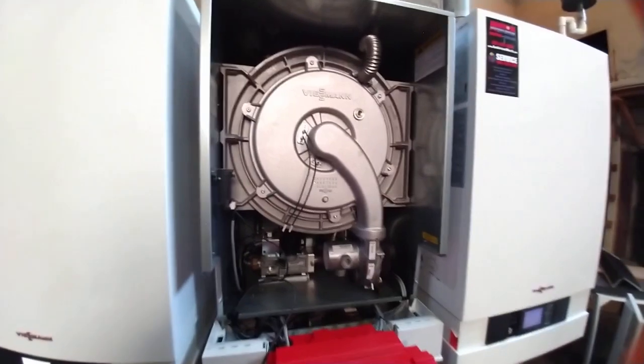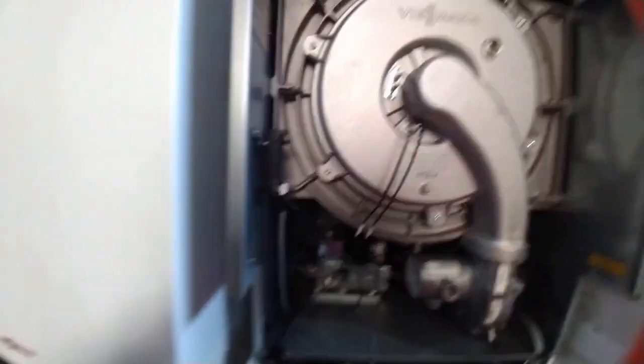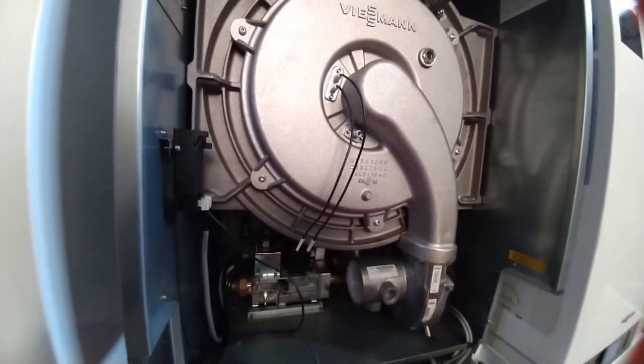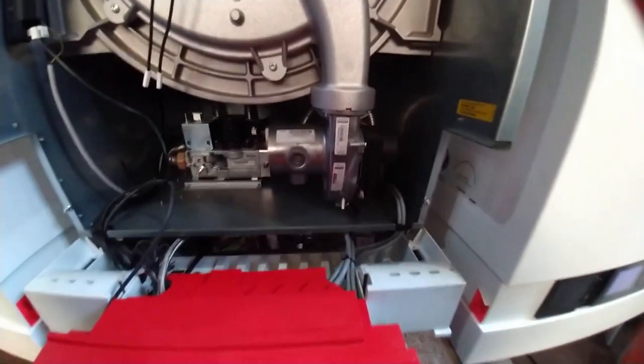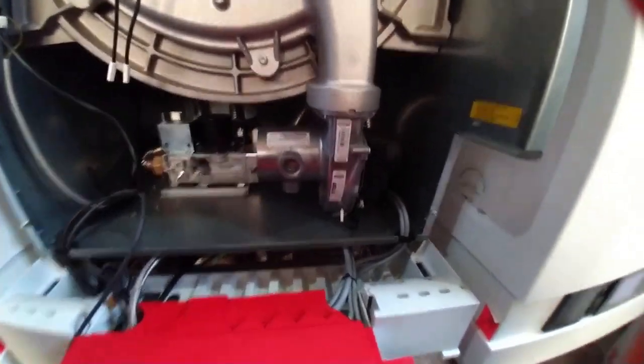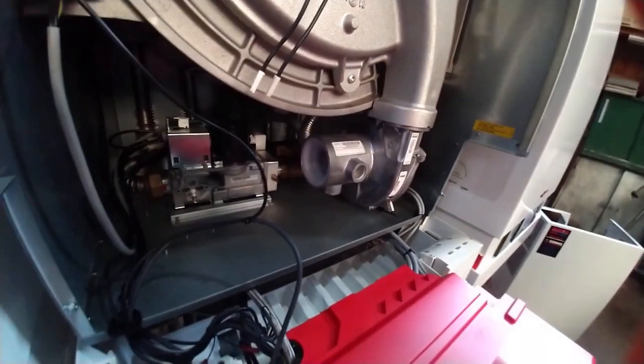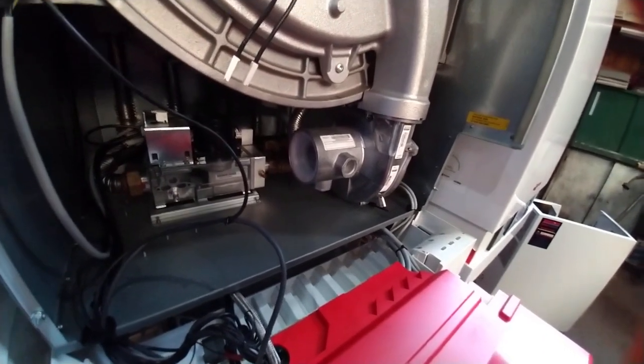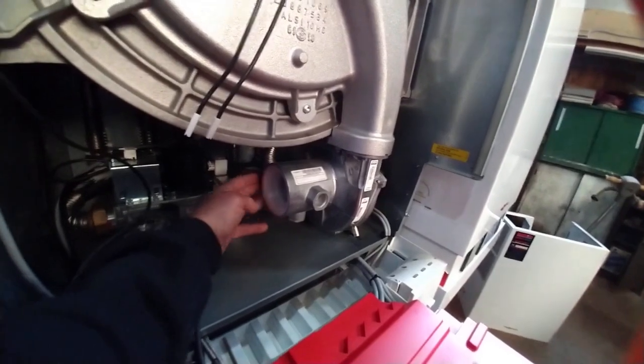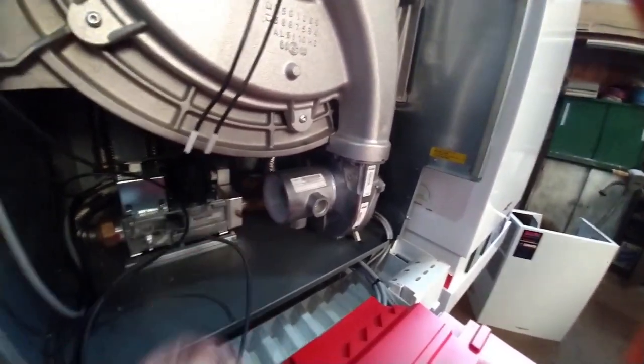So in order to inspect the heat exchanger, we've got to disconnect the wiring for the flame rod and igniter. We have to disconnect the wires from the gas valve, and then we have to go behind and disconnect the gas line coming into the mixing portion here between the gas valve and this venturi.